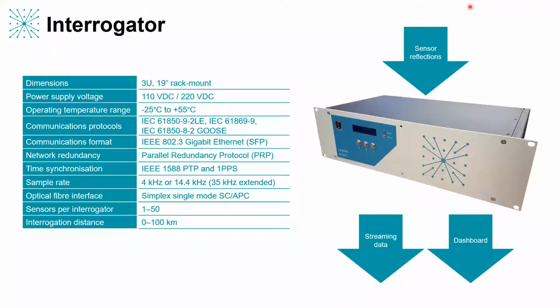I won't spend too much time on this, but as you can see, the interrogator is a standard 3U rack mount system, generally sits in the protection and control rack, takes a standard DC voltage supply, and is compliant with the usual modern interoperability standards defined by 61850, for example, LE and GOOSE, moving to 61869-9. It's based on Gigabit Ethernet. We use PRP for redundancy, and we use 1588 PTP or pulse per second for time sync. Standard is that we sample at 4 kilohertz or 14.4 kilohertz, depending on whether it's a protection or metering application. But for extended applications, we can spec this up to a maximum sample rate per sensor of 35 kilohertz, giving us a bandwidth of 17 kilohertz per sensor, which is excellent for, for example, power quality applications.